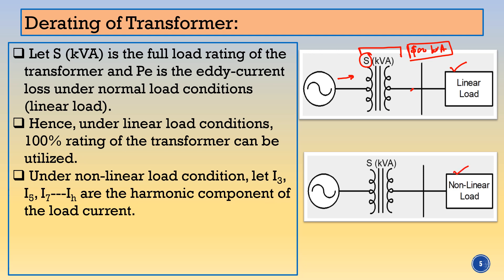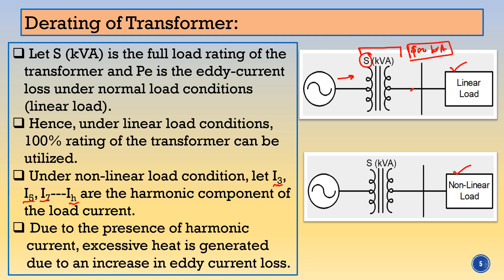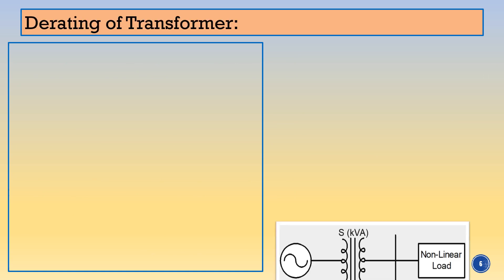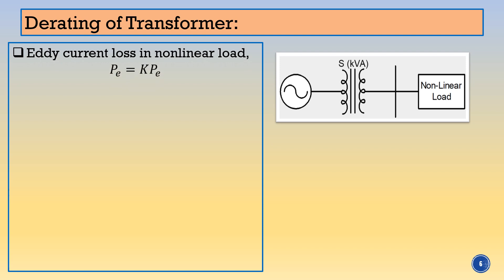Under the nonlinear load — suppose instead of linear load, a nonlinear load such as computer load or power electronic drives, adjustable speed drives are connected. As the nonlinear load is connected, it carries harmonic components of the current: third, fifth, seventh harmonics, likewise up to the H-th harmonic. We can consider up to the 50th harmonic. Due to the presence of this harmonic current, excessive heat is generated. Hence the transformer must run on derating. Eddy current losses under the nonlinear load PEN = K × PE, so it is going to increase.